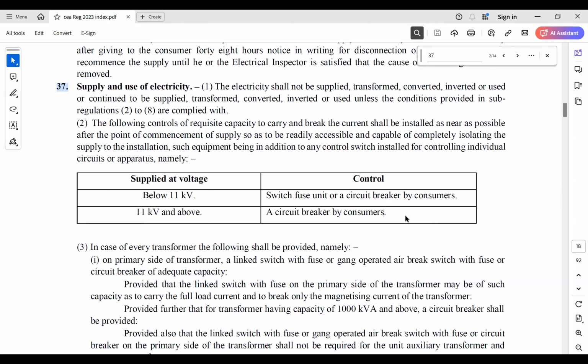On the LT side also, once again, there is a circuit breaker. Now, what is happening is that there are multiple circuit breakers serving the same function. If you see, there is a circuit breaker in the ring main unit, there is a circuit breaker before the transformer, then there is a circuit breaker after the transformer.